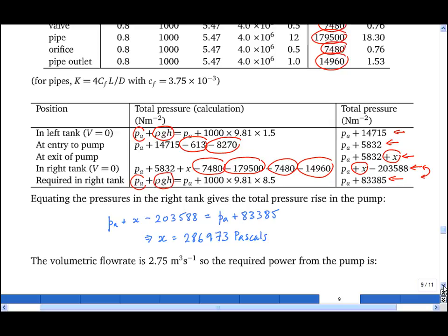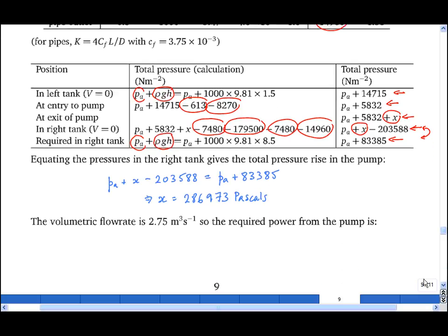And to get the required power from the pump, we multiply this by the volumetric flow rate, 2.75 meters cubed per second times 286,973 pascals, which is a newton per meter squared. And that gives us 789.2 kilowatts.